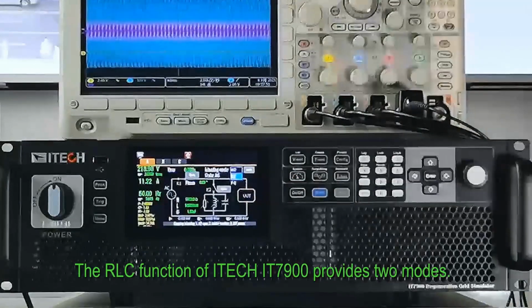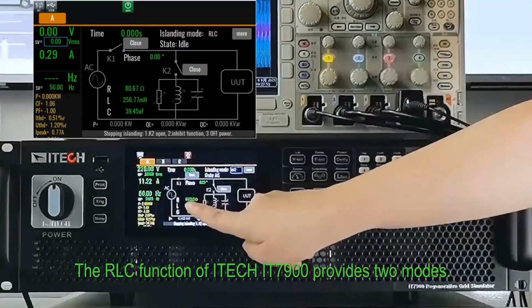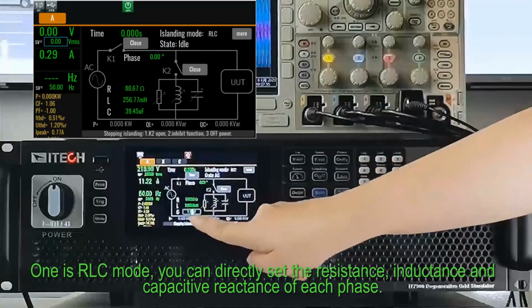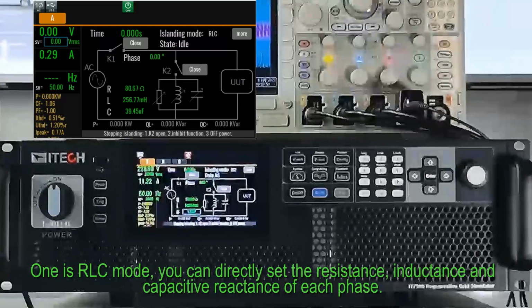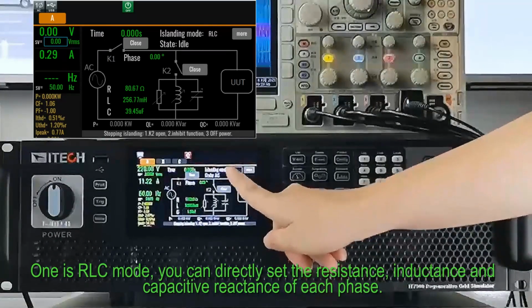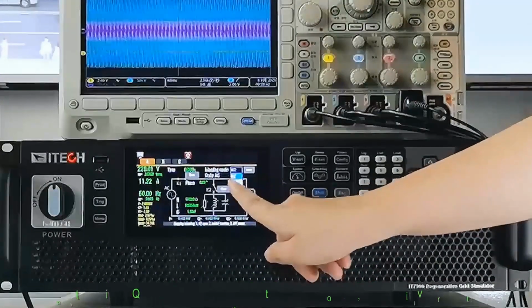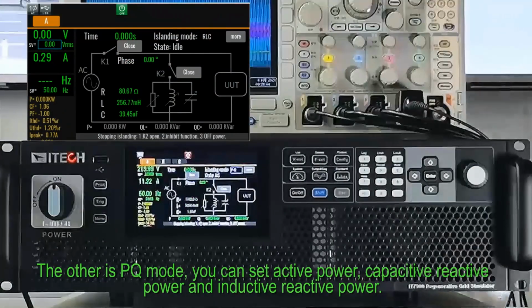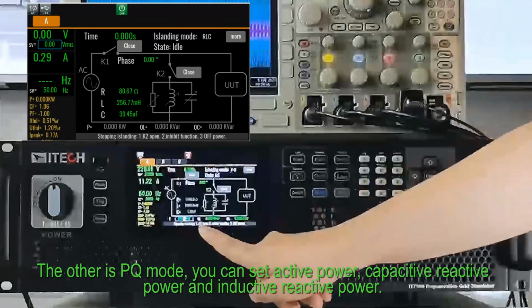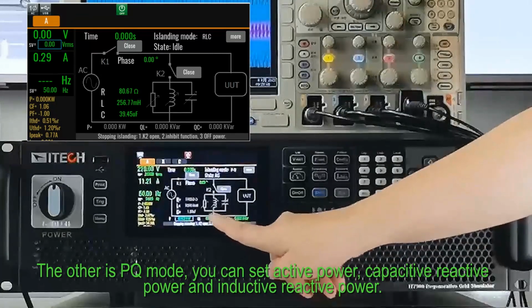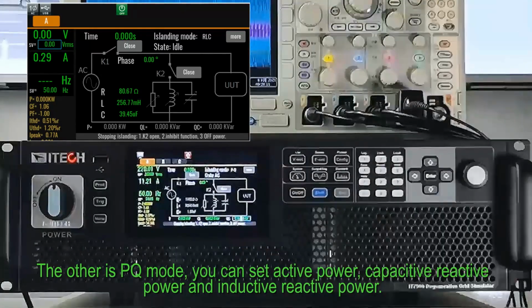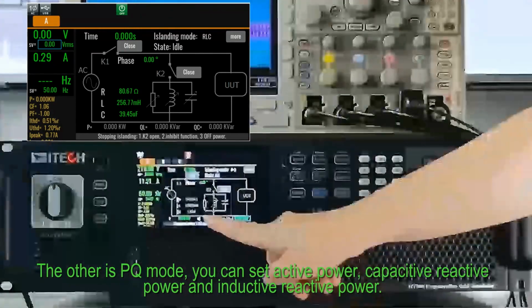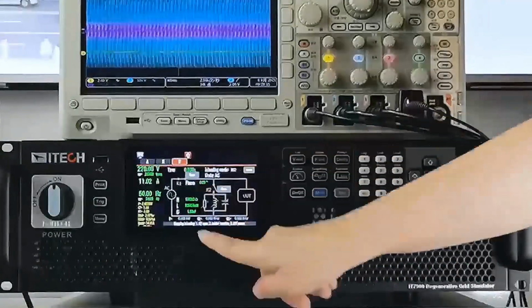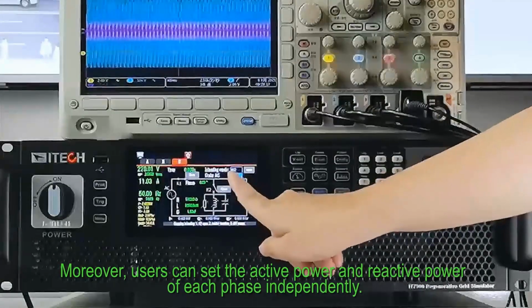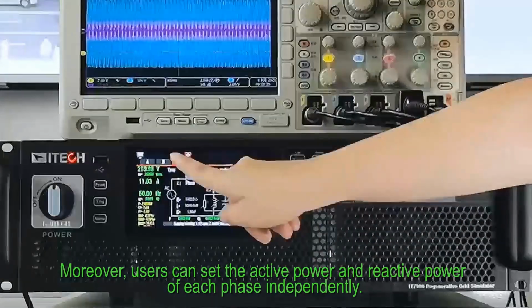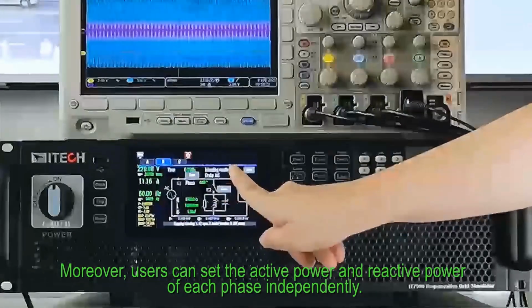The RLC function of IT7900 provides two modes. One is RLC mode. You can directly set the resistance, inductance and capacitive reactance of each phase. The other is PQ mode. You can set active power, capacitive reactive power, and inductive reactive power. Moreover, users can set the active power and reactive power of each phase independently.